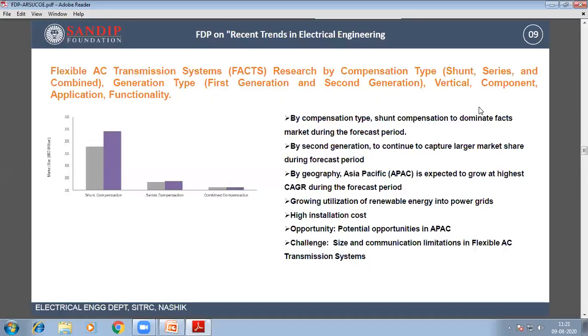In shunt compensation, the FACTS devices are connected in parallel with the power system or transmission line. Shunt compensation is actively used in power transmission and distribution networks to reduce power losses and voltage drop - that is widely known. Moreover, shunt compensation is used for various applications because of its ability to support voltage stabilization, dynamic reactive power control, increase transmission capacity, power system damping oscillation, transient stability, system voltage balancing maintenance, reduce transmission losses and voltage control. These parameters are very important as far as transmission utilities are concerned, which is why shunt compensation is popular compared to other options.